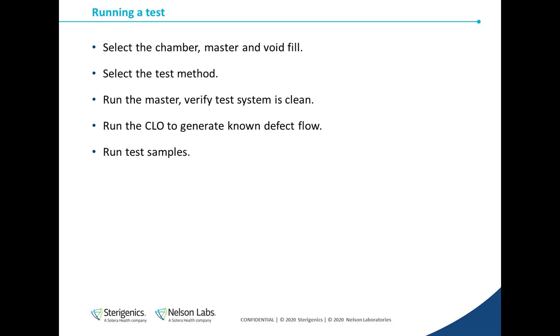Now, let's go over how a typical test would be run. First, we would select the chamber, the master, and the void fill that most closely represents the test samples from our library of accessories. Then we would pick the test method. As we talked about earlier, the methods are customized for the sample type. So if our sample was a vial, then we would pick the method that we have validated for vials.